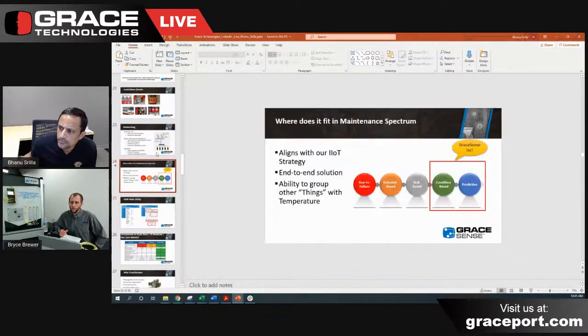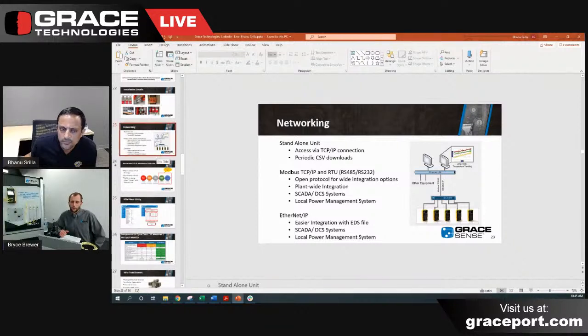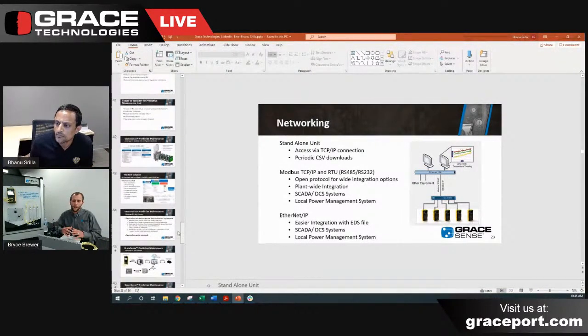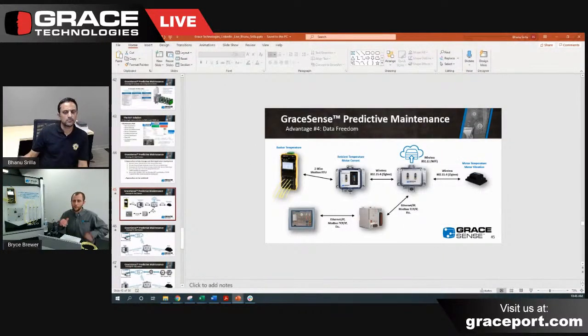From the Modbus RTU side, that can be brought into a cloud-based system as well—we have our GraceSense predictive maintenance line. The hotspot monitor is part of that, but it can be absorbed into the rest of the product line, so you can have a central location to bring in multiple hotspot monitors and view the trend over time, set up alarms that go out via email or text. From the rest of the family there's also vibration monitoring for motors, which are high-attention items that facilities are usually keyed in on. That's why we like to bring it all together, to bring awareness to the electrical side that's often neglected.